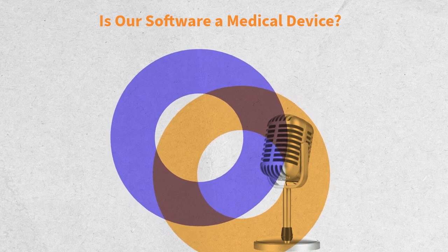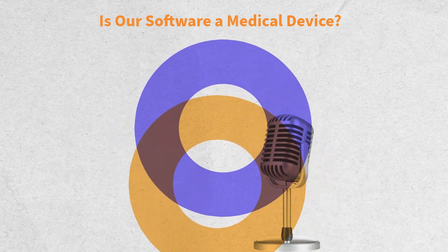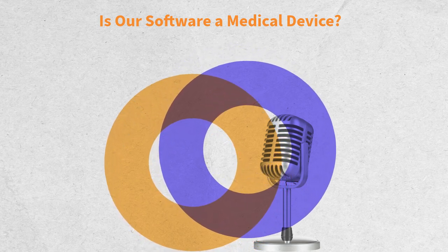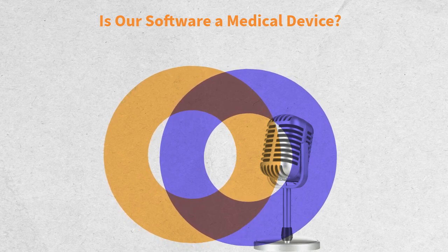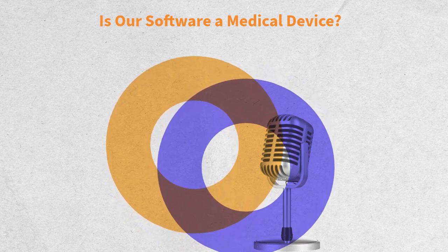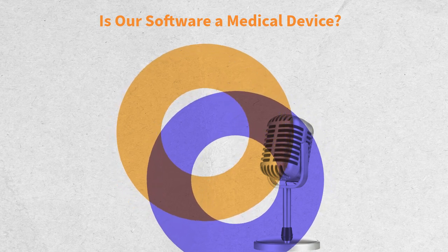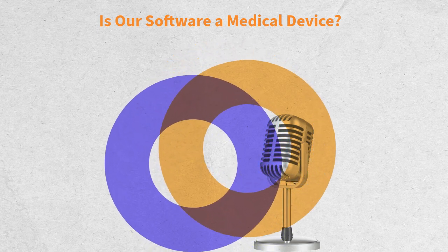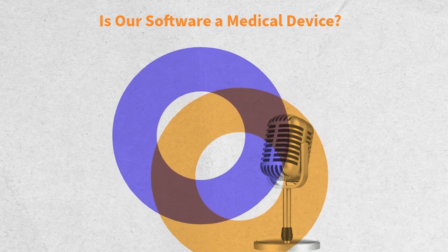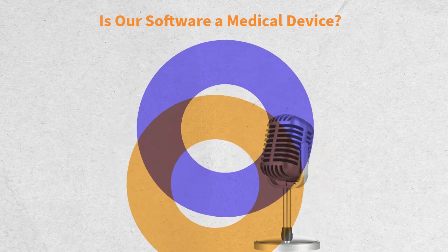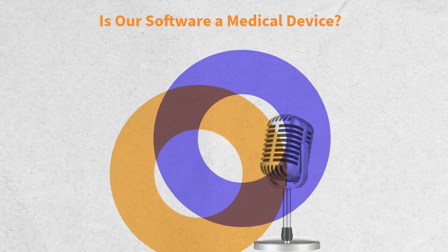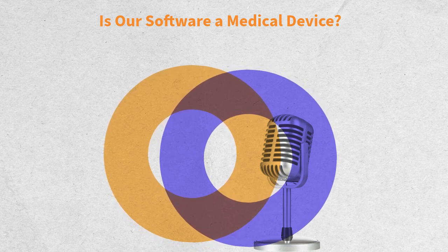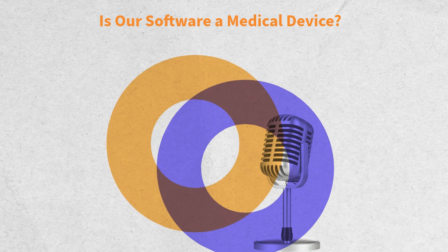This means that before, many solutions could slip into Class 1. Now they require the evaluation by a notified body and much more rigorous documentation. Should a software used by physicians always be certified as a medical device? Absolutely not. If the software is a mere managing or administrative tool, a digital diary, data filing with no clinical analysis, certification is not needed. Only when it helps diagnosis or decisions on therapies, the MDR obligation applies.